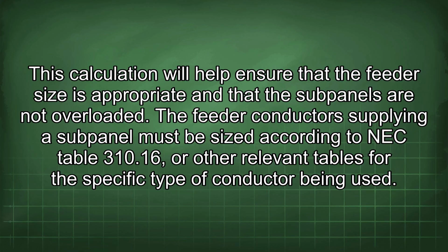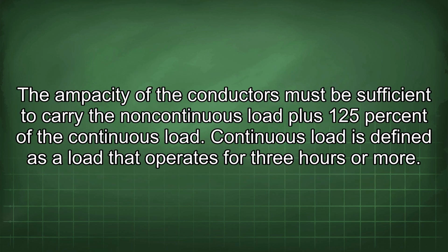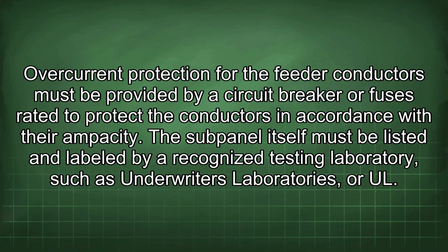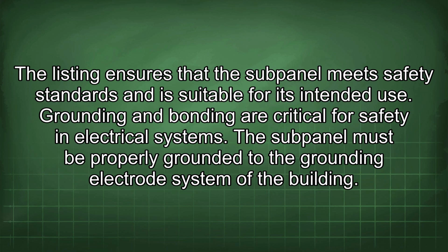The feeder conductors supplying a subpanel must be sized according to NEC Table 310.16 or other relevant tables for the specific type of conductor being used. The ampacity of the conductors must be sufficient to carry the non-continuous load plus 125% of the continuous load. Continuous load is defined as a load that operates for 3 hours or more. Overcurrent protection for the feeder conductors must be provided by a circuit breaker or fuses rated to protect the conductors in accordance with their ampacity. The subpanel itself must be listed and labeled by a recognized testing laboratory, such as Underwriters Laboratories or UL. The listing ensures that the subpanel meets safety standards and is suitable for its intended use.